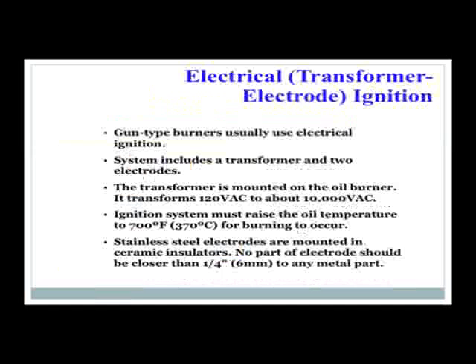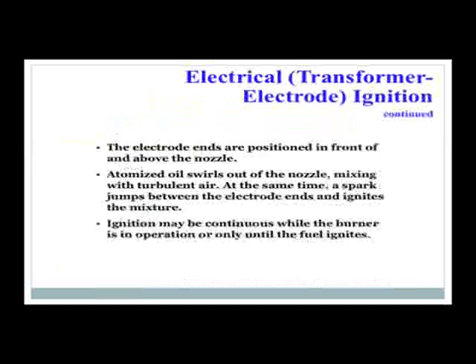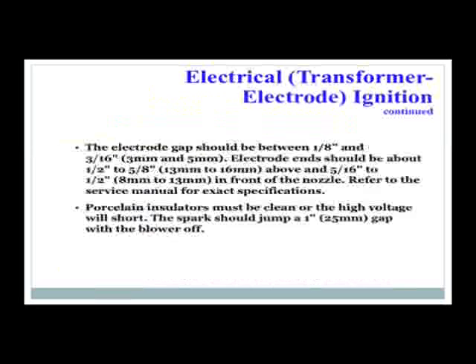No part of the electrode should be closer than 1/4 inch to any metal part, or the ignition spark will go the wrong direction. The electrode ends are positioned in front and above the nozzle. Atomized oil swirls out of the nozzle, mixing with turbulent air. At the same time, a spark jumps between the electrode ends and ignites the mixture. Ignition may be continuous while the burner is in operation, or only until the fuel ignites.